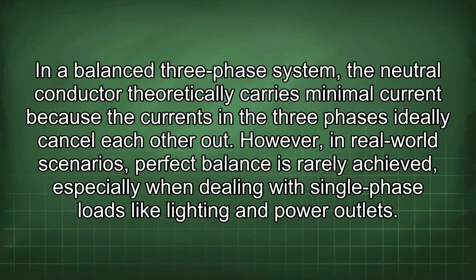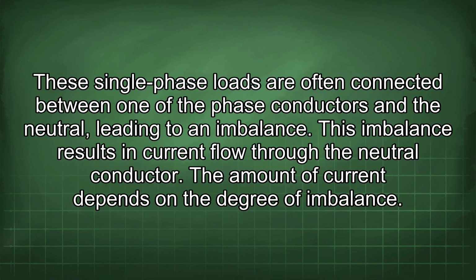In a balanced three-phase system, the neutral conductor theoretically carries minimal current because the currents in the three phases ideally cancel each other out. However, in real-world scenarios, perfect balance is rarely achieved, especially when dealing with single-phase loads like lighting and power outlets. These single-phase loads are often connected between one of the phase conductors and the neutral, leading to an imbalance. This imbalance results in current flow through the neutral conductor. The amount of current depends on the degree of imbalance.